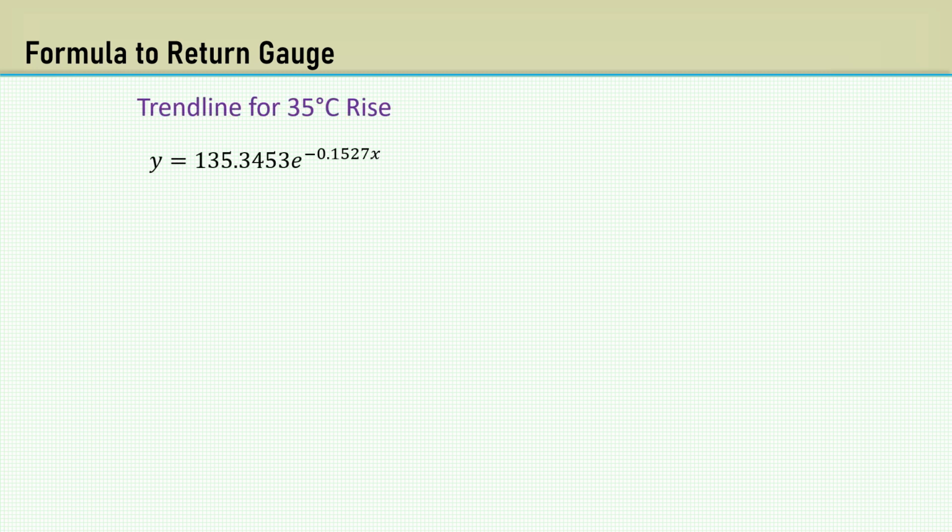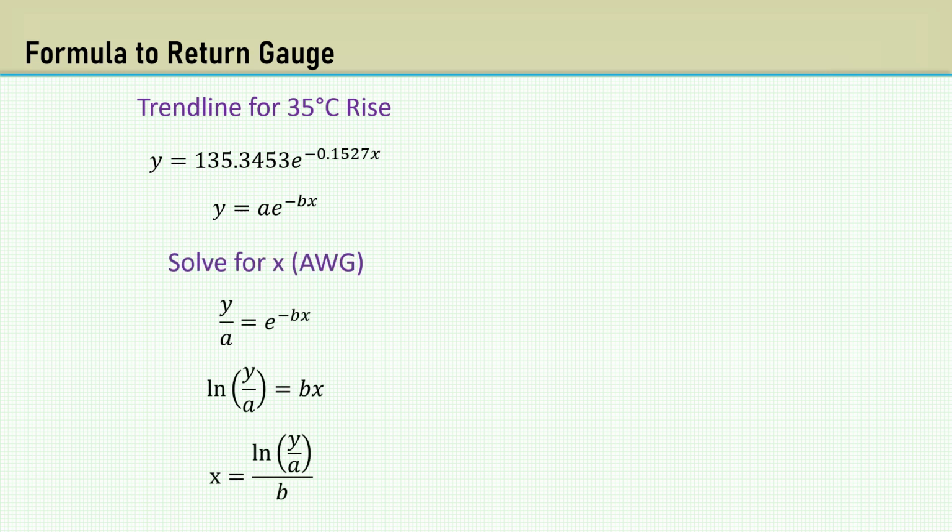Let's make a formula to return the wire gauge for a specific current and temperature rise. Here's the trend line for the 35-degree plot. We can express it in a general form, like this, which has A as the coefficient. We then rearrange to solve for X, which is the wire gauge.